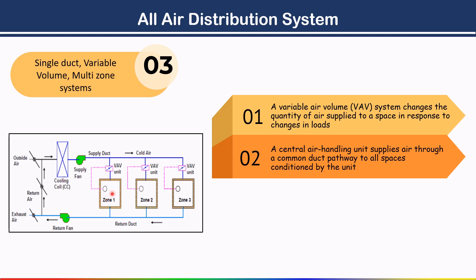Suppose in zone one, the heat load calculation requires 1000 CFM. This was designed for 10 people sitting in the space. However, if the number of people decreases for some reason, we need to supply less than 1000 CFM of conditioned air.